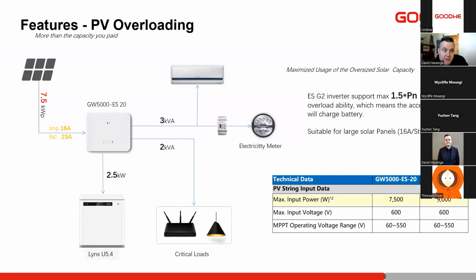Our hybrid inverters offer PV overloading. The new ETs as well as the ESG2 have this feature. What we mean with PV overloading is that you can put 1.5 times PV on the inverter, and that is usable PV. You can oversize it even larger than that for oversizing's sake, but the usable PV on this inverter is 1.5 times the inverter rating. So on the 5 kilowatt inverter, we can use 7.5 kilowatts of PV. That will give us our 5 kilowatts of AC while simultaneously charging at 2.5 kilowatts.